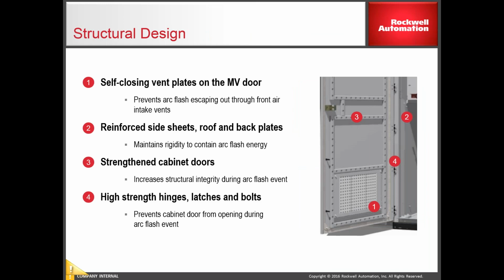So if we look at the structural design, we've got some self-closing vents in front of the door. So in the event of a fault, those vents are going to close off, preventing any gases or any shrapnel, any type of debris from escaping the drive. We've reinforced the side sheets and the roof plates on the drive, and we've strengthened the cabinet doors. If you look at the extra bracing that we have on these doors now. And we've also modified the hinges. That will prevent the door from opening in the event of a fault.